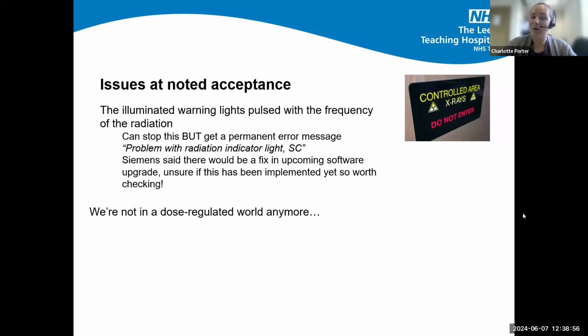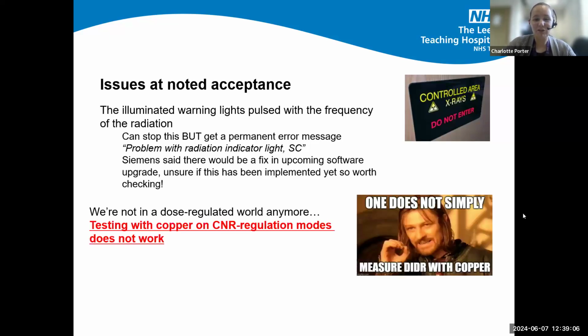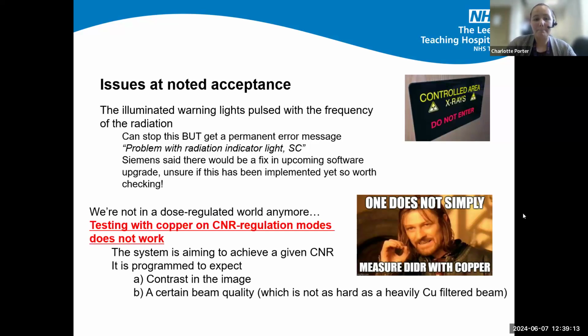Then obviously it goes without saying, we're not necessarily in a dose-regulated world anymore. We found very quickly that all of our detector input dose rate testing with copper did not work. I'm not going to dwell on this because I know that Greg's going to speak about the QA side of things a lot more in a few minutes. But the system is aiming to achieve a given CNR, as I've said, so it's expecting contrast in the image. So if you give it a flat field, then it's going to struggle. And it is also expecting a certain beam quality, which is certainly not the hard beam that you get when we put a lot of copper into it.